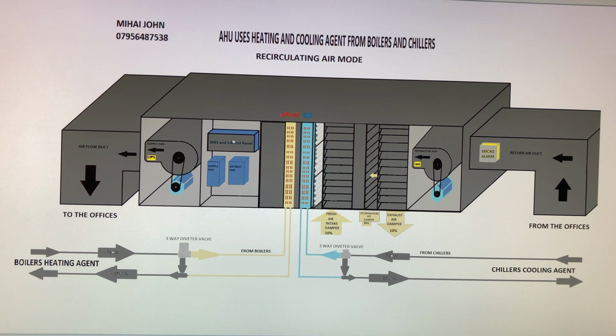We also have the building management control, which is actually the brain of the air handling unit, which controls the air handling unit. We have inverters, sometimes we don't, but this one particularly has inverters. So the inverter will take the information from the building management control, and it will control the speed of the supply fan and the speed of the extractor fan. This is an economical issue.